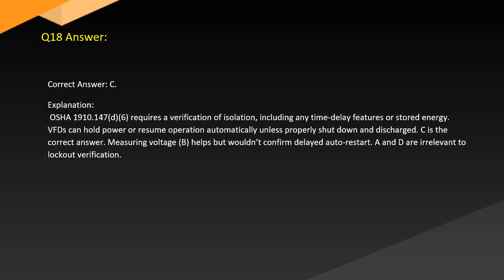Answer. Correct answer: C. Explanation: OSHA 1910.147 D6 requires a verification of isolation, including any time delay features or stored energy. VFDs can hold power or resume operation automatically unless properly shut down and discharged. C is the correct answer. Measuring voltage, B, helps but wouldn't confirm delayed auto restart. A and D are irrelevant to lockout verification.